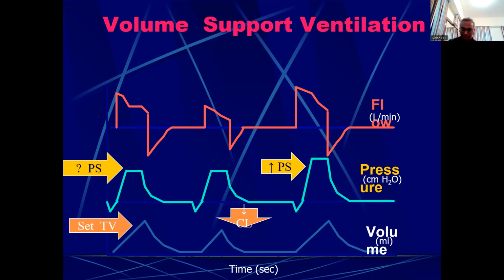Yeah, makes sense. Otherwise, there won't be any flow at all. So this will restore the tidal volume and it becomes a closed loop ventilation, in the sense that it will keep changing the pressure support to achieve the target tidal volume. So this is also called volume target or volume guarantee or mandatory minute ventilation. In certain ventilators, it is called mandatory minute ventilation.